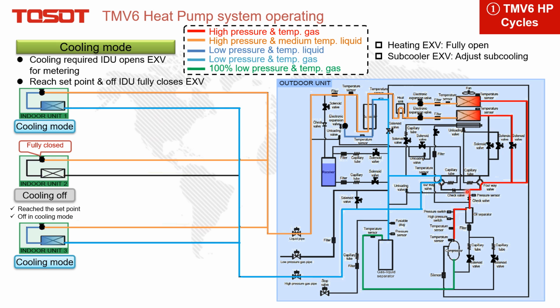And last, you may wonder, how about the refrigerant flow to the four-way valve? Actually, you can find that the other end of the four-way valve is connected with a capillary, which means the refrigerant cannot get through it, just like this.